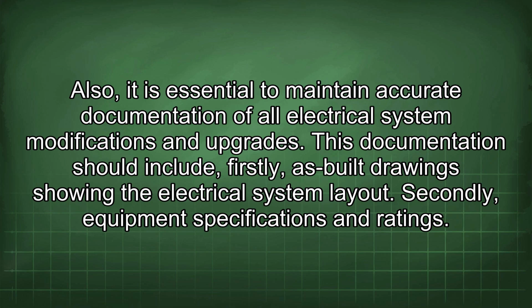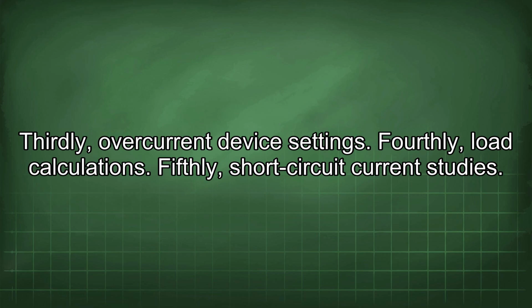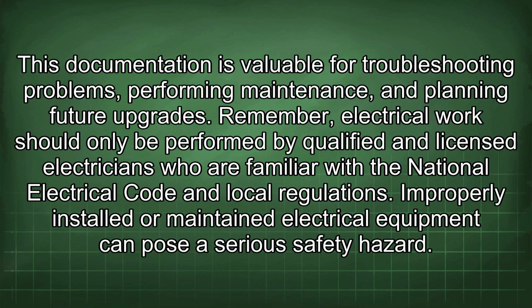Also, it is essential to maintain accurate documentation of all electrical system modifications and upgrades. This documentation should include, firstly, the single line drawing showing the electrical system layout. Secondly, equipment specifications and ratings. Thirdly, overcurrent device settings. Fourthly, load calculations. Fifthly, short-circuit current studies. This documentation is valuable for troubleshooting problems, performing maintenance, and planning future upgrades.